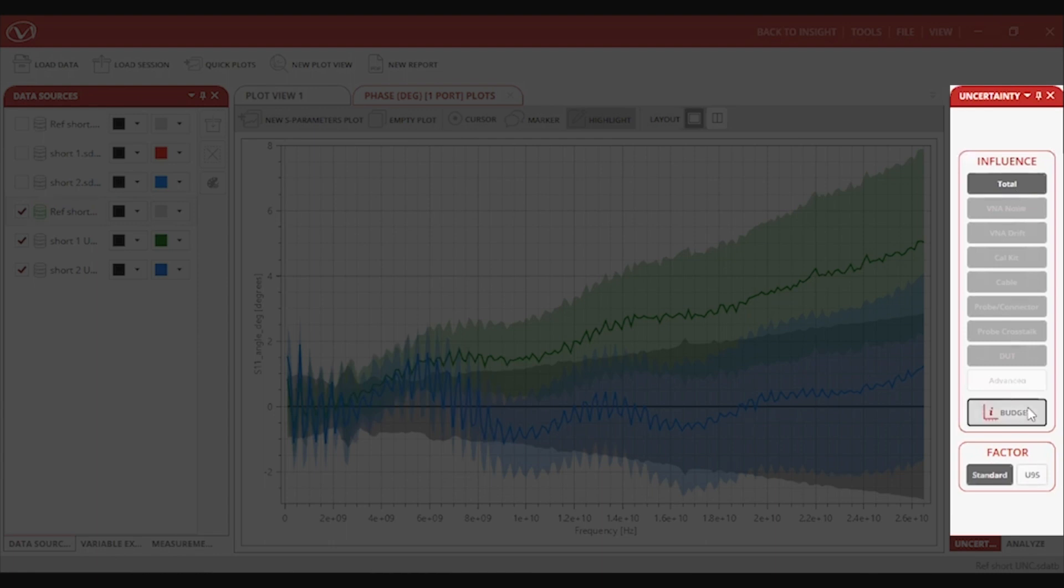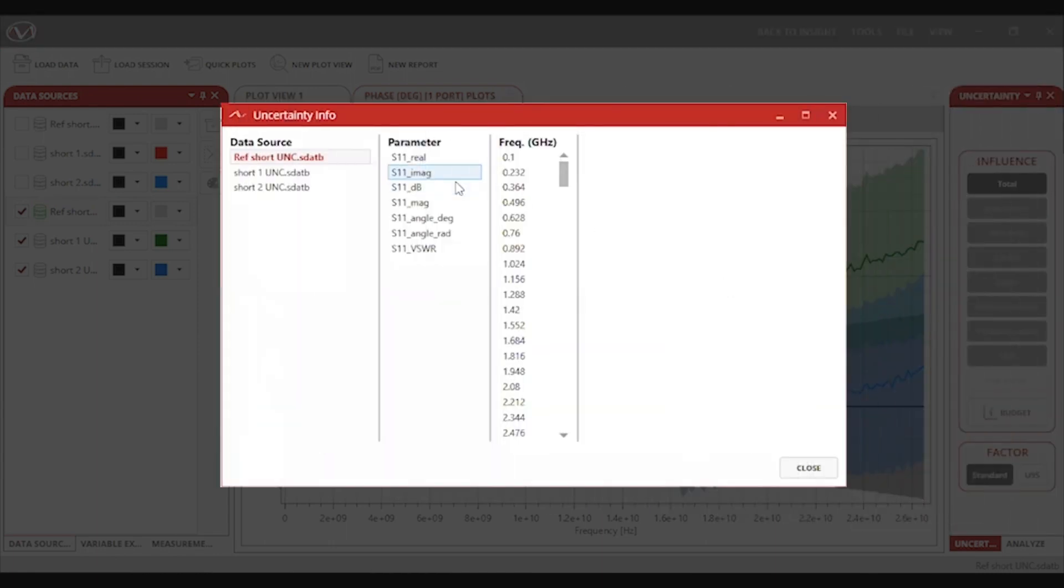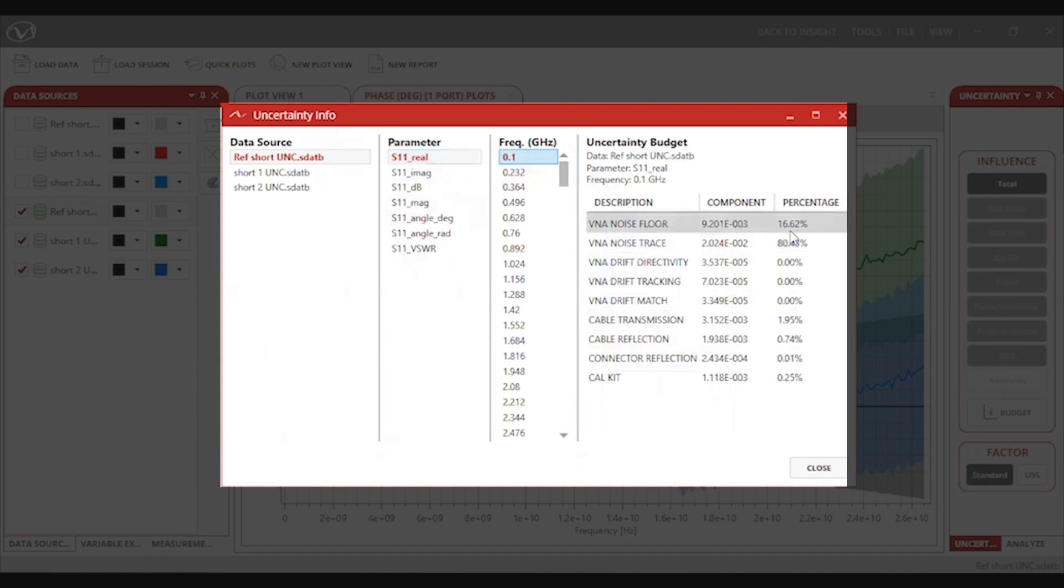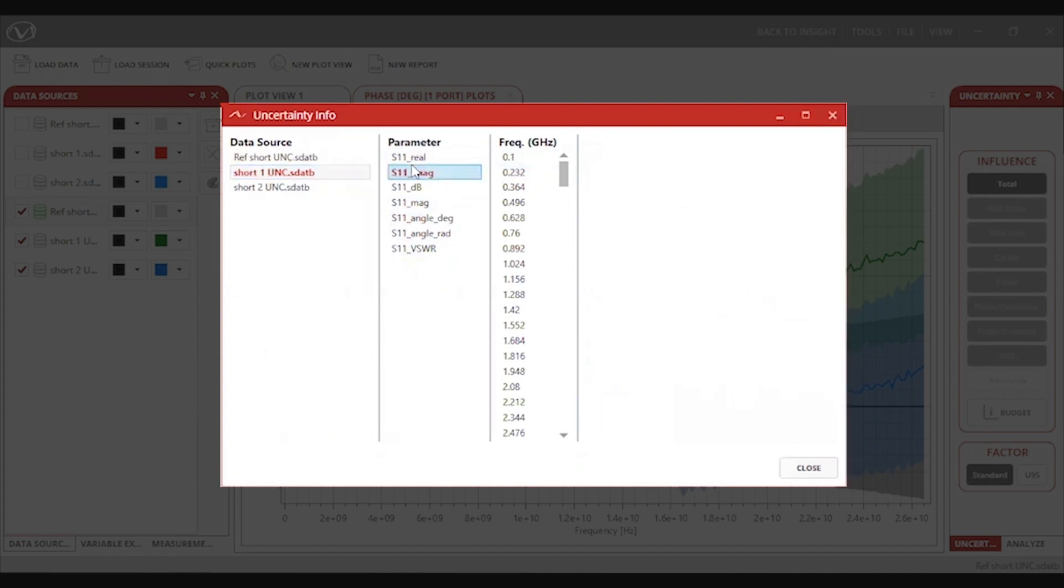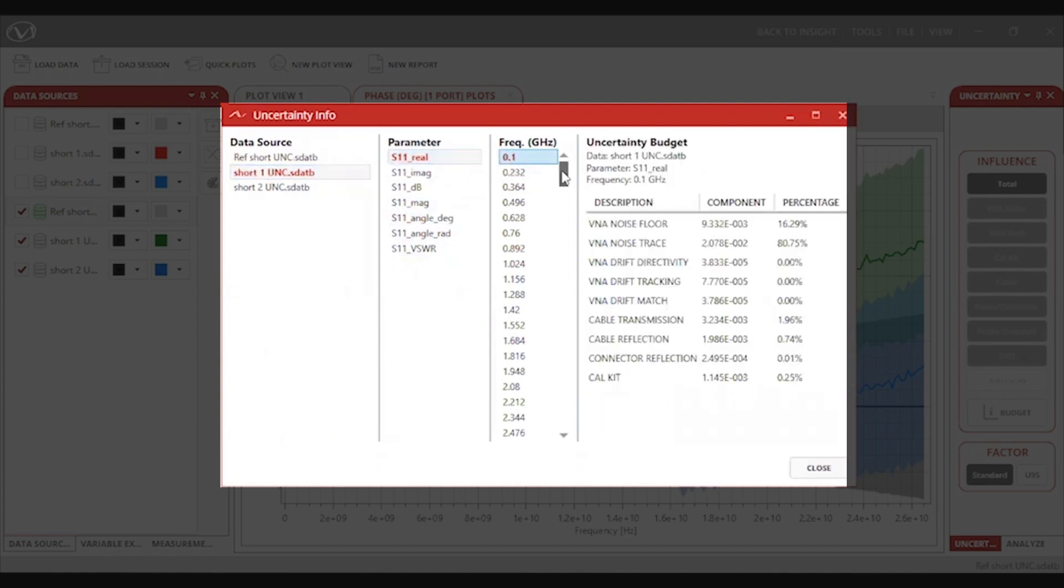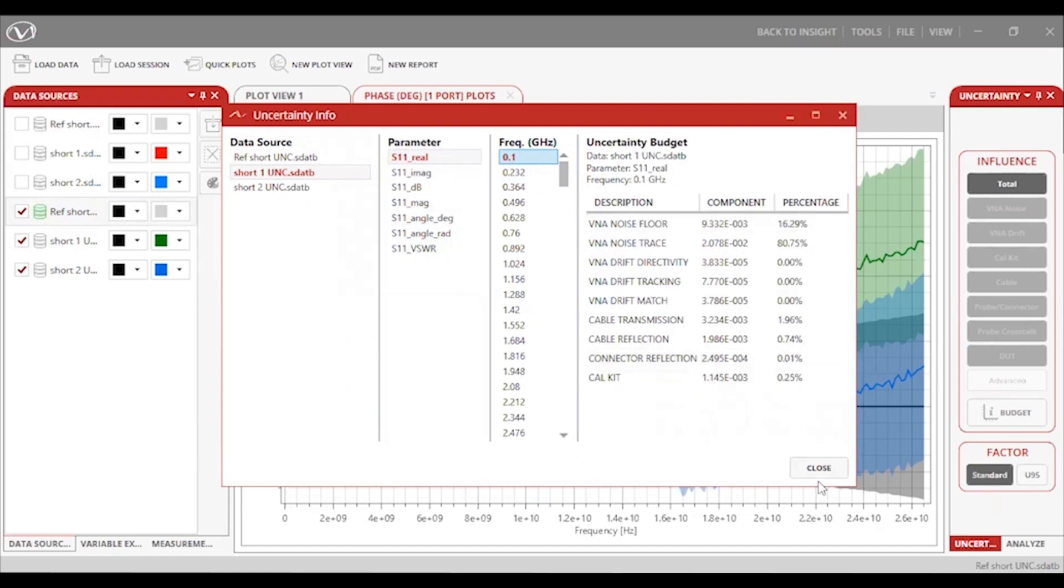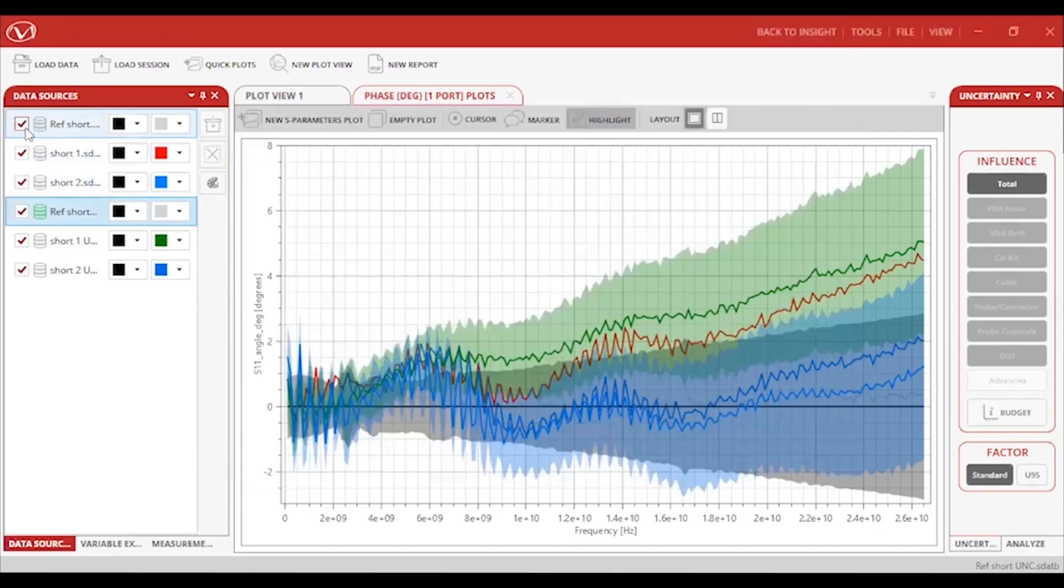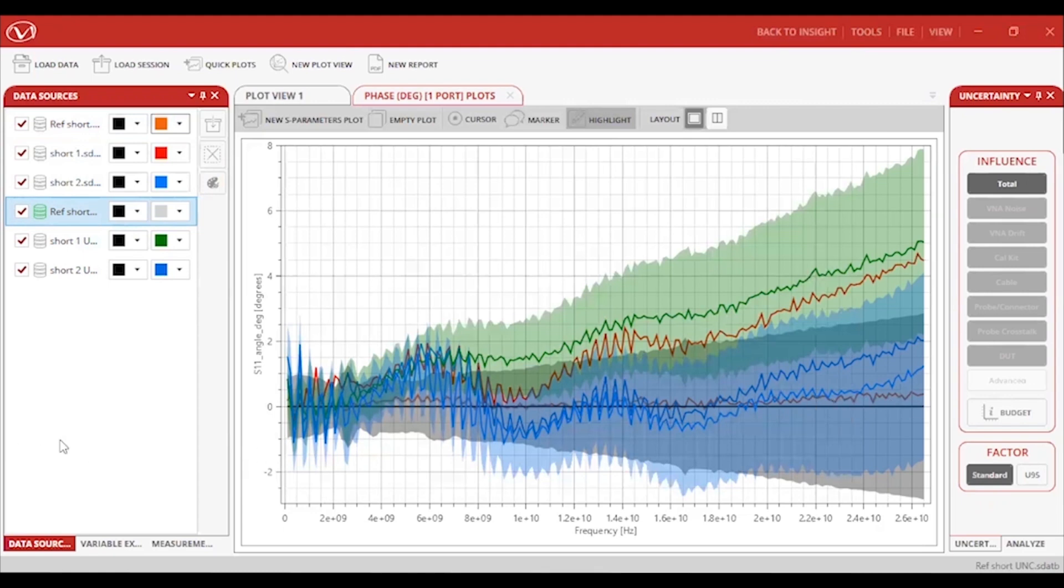In the budget pop-up window, it displays the individual uncertainty contributions coming from the equipment that was characterized. The uncertainty budget can help pinpoint the source of inaccuracy in your calibration so that you know exactly what to change about your setup to improve your system performance. For example, if the cable is a source of max uncertainty, you now know what to replace rather than having to troubleshoot other components in the system, which can be a huge addition to the capabilities of the 8510.